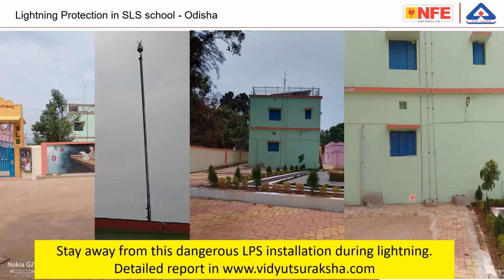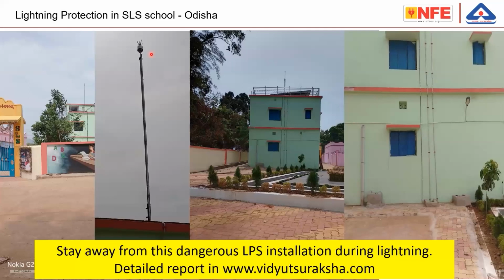Not only is the violation on the down conductor and the earthing, the violation is also on the air termination system. One of our volunteers from NFE went to this particular school, and he had a talk with some of the villagers. And the villagers are under the impression that this rod, where I'm moving the cursor, is going to protect not only the school building, but about 117 meters all around the school. So this rod is installed, and a story has been given to the villagers that the whole area is protected, which is also a non-standard installation or a non-standard theory.